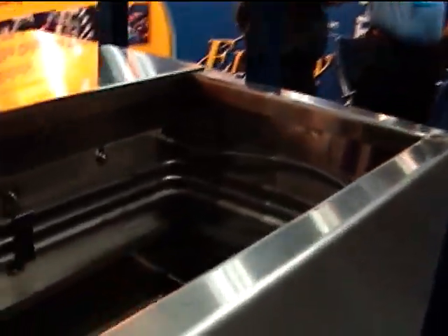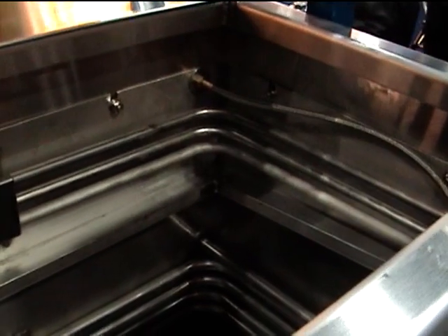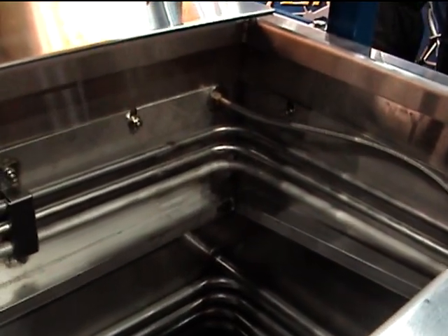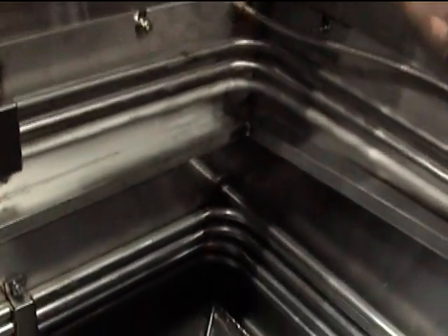I'll walk around the backside of the machine. This here is the refrigeration system. One refrigeration system for each of the two sets of cooling coils. So when you look in here, you'll see that there's the top coil. Here we call that the vapor trap because it runs colder, and you have the lower set of coils.